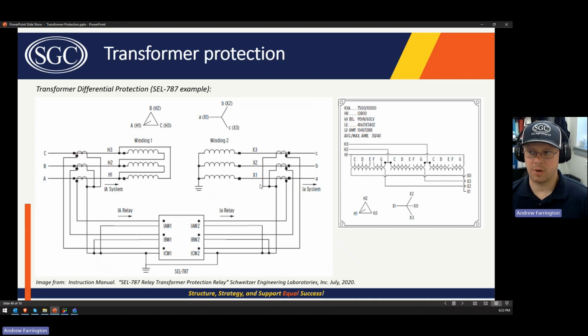How do we know that a compensation needs to be made? Well, this is a delta Y transformer. So that has a couple of properties. We know that there's going to be a 30 degree phase shift one way or the other. So we need to account for that. We need to set that to yes to account for that phase shift.